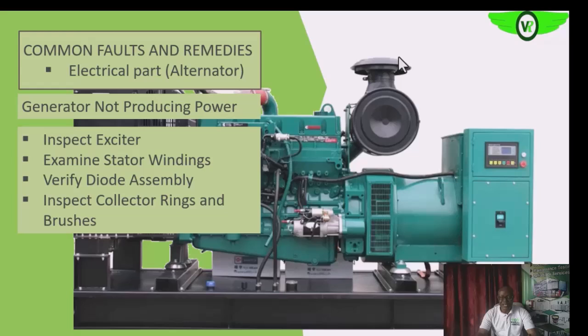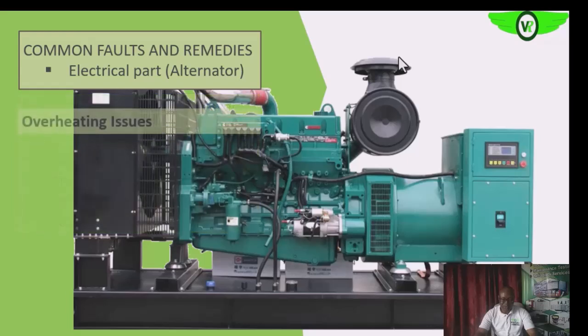For generators with static excitation systems that use slip rings: if the brushes are not making proper contact with the slip rings, the excitation voltage from the exciter will not be available to the field to produce the magnetism it needs. We want to check the brush and slip ring assembly to ensure that appropriate pressure is maintained and that the brush is not worn out at those contact points.